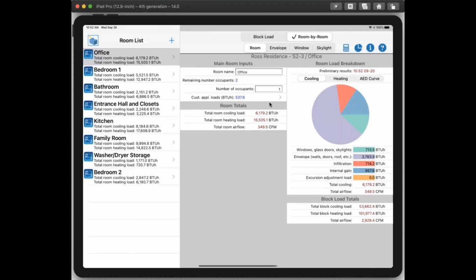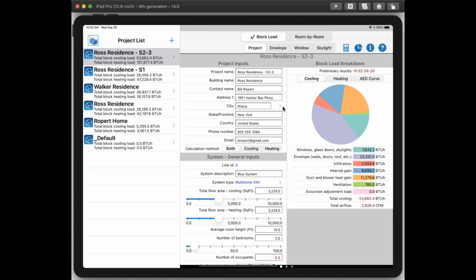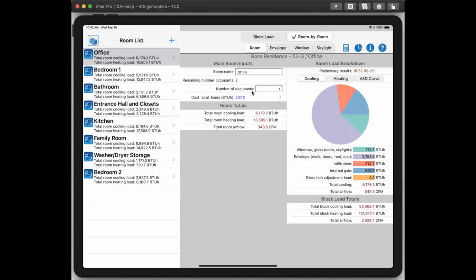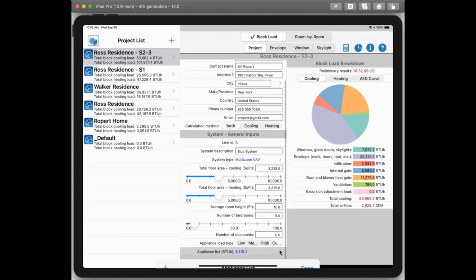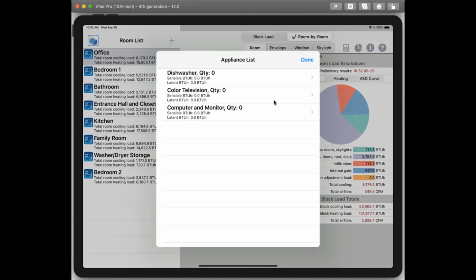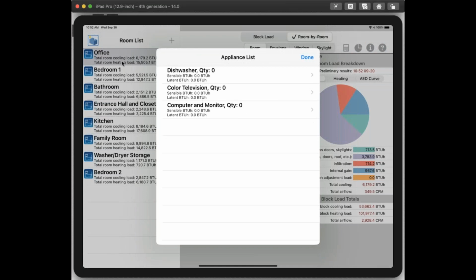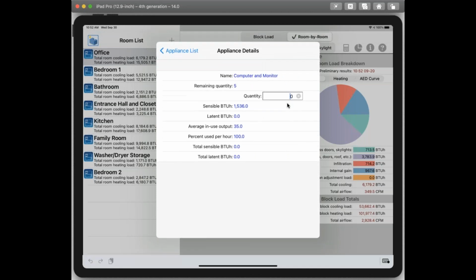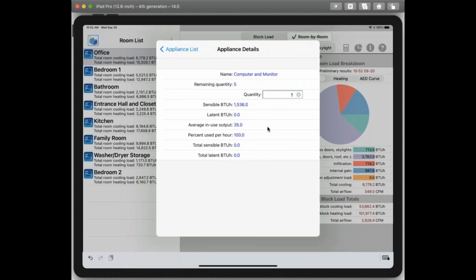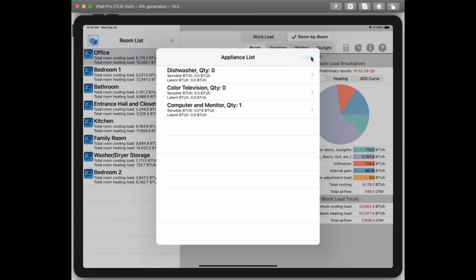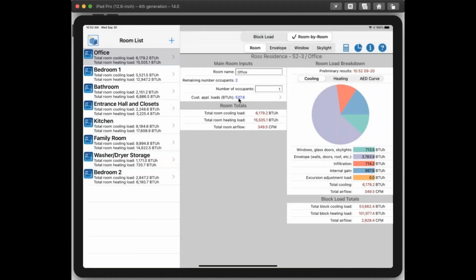So here I have an office. I can assign the number of occupants. Remember, I had 6 occupants total, so I can start assigning occupants to my different rooms, and it adds the sensible and latent load for that person. Then, remember I defined these appliance loads in my appliance list. Now I can start parsing out these appliances to the individual rooms. Since this is an office, I'll say I have 1 computer here, and it assigns that computer load to this room. Then I can do that for the remaining rooms.